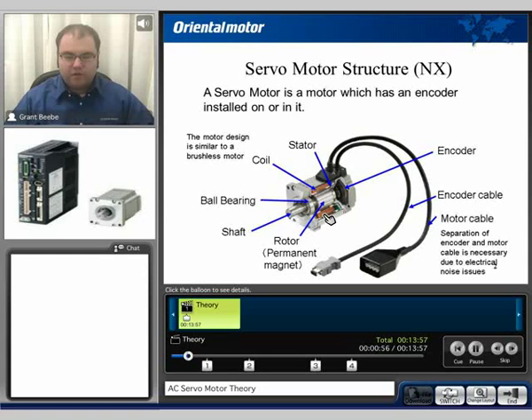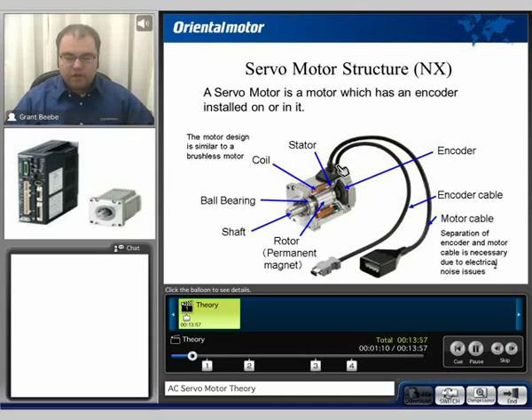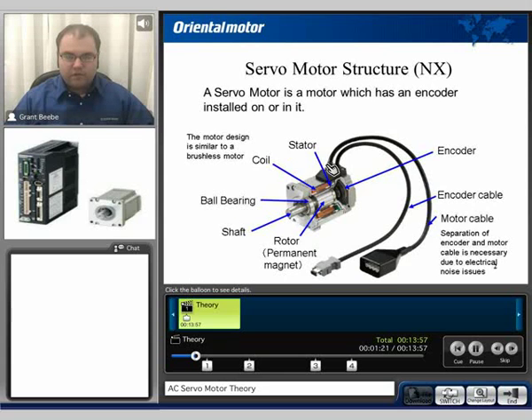What makes a servomotor a servomotor is the inclusion of an encoder, which is located usually at the end part of the motor. We also have two separate lines coming out for the motor signals — one for the encoder and one for the motor, which would be typically a three-phase winding configuration. These are separated in order to lessen the effects of electrical interference and noise.